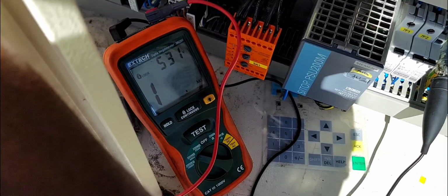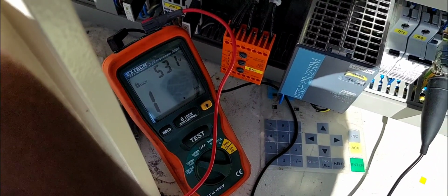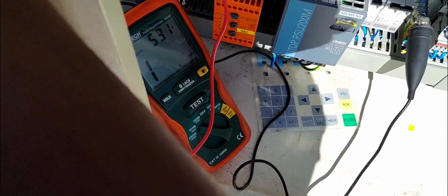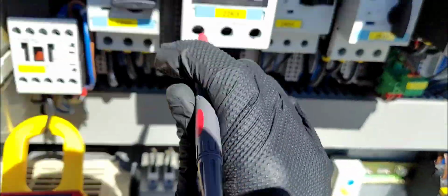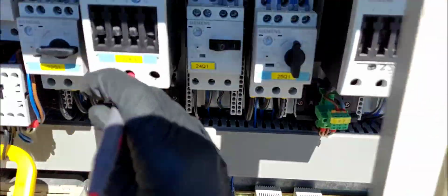I'm gonna go ahead now and hit here. Look at my meter. That's good. The 1 on the screen means it's overload, infinity. It's higher than 200 megs. So that's good. I'm checking all 3 windings, all 3 terminals. All 3 of them are good.